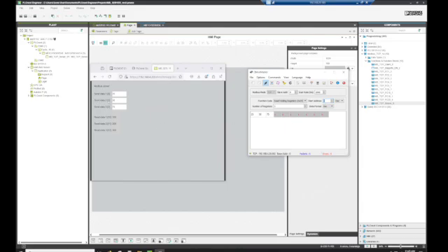We're starting at address 0 simply because the Modbus server is putting that data into register 0, register 1, and register 2. Now let's say we want to send the server some data. So we are going to switch over to write multiple registers. Now we're going from reading registers to writing registers. And because the start address is now 10, we have to have the start address be 10. That's just moving the array around so that we can put values into the right spots. If you'll notice, I've already written 100, 200, and 300. If I change this to 20, 30, and 40, and then we go ahead and do a write, you'll notice that we now have 20, 30, and 40 in the read data tab.